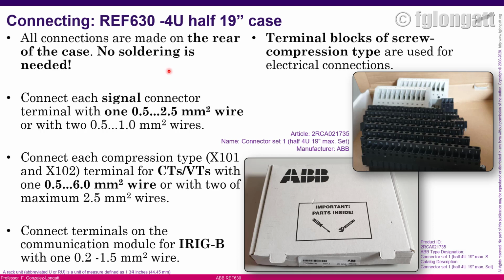Depending on the terminal we are working with, the wire needed has a different specification. We have some wire for signals, some wire for CT and VT, and some wiring for communication. As you can see in this slide, if we are working with signals, we can use a single wire between half and 2.5 square millimeters. If we are using CT and VT, we need to use between half and 6 square millimeter wire.